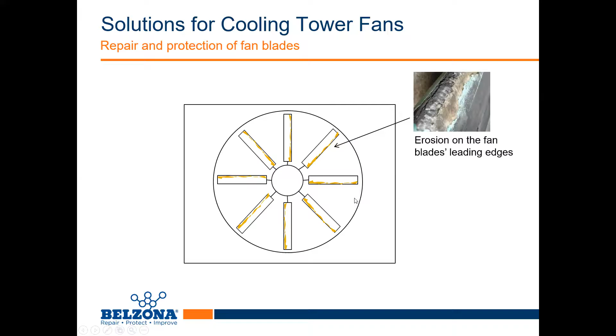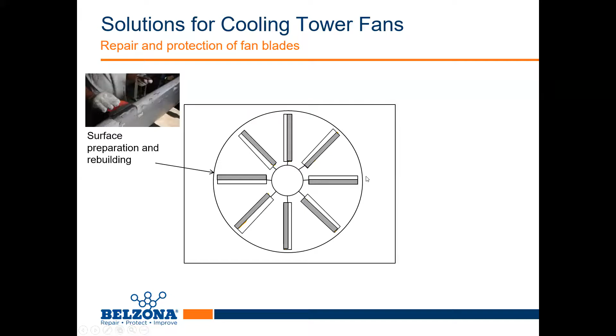So in this diagram, this is what you'll typically see, erosion on the fan blades. Here we are with some surface preparation. We're also going to use either an MEK or a Belzona 9111 cleaner degreaser to get rid of any oil or grease and contamination on this surface prior to doing this type of prep. And you're seeing the application of 1121, which is a typical product that we'll use to rebuild, especially on metal fan blades.